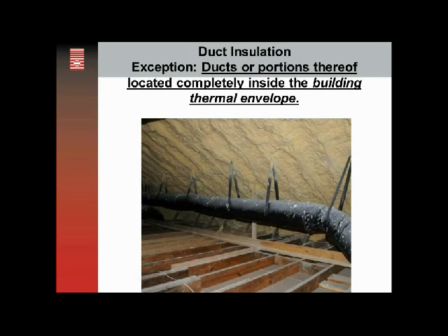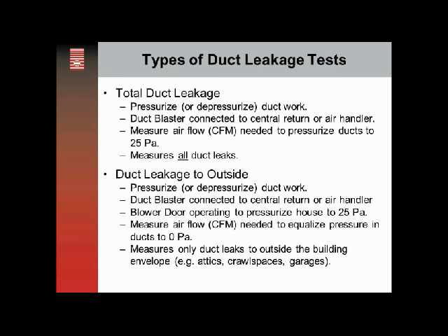Questions you're going to have to ask yourself out there when you're looking at both insulation or whether or not you're even testing: is the ductwork inside the envelope, or is it outside the conditioned envelope? Here's a shot of a conditioned attic assembly and a duct run going through it.